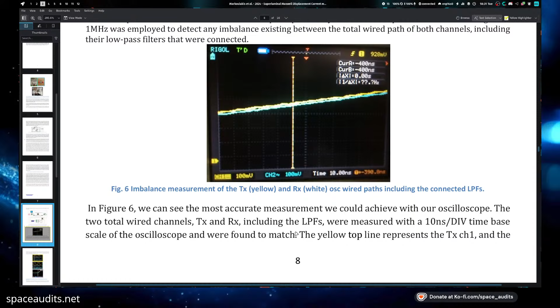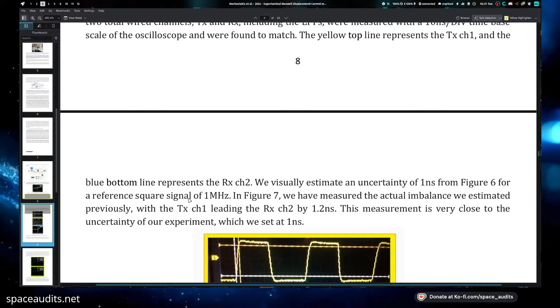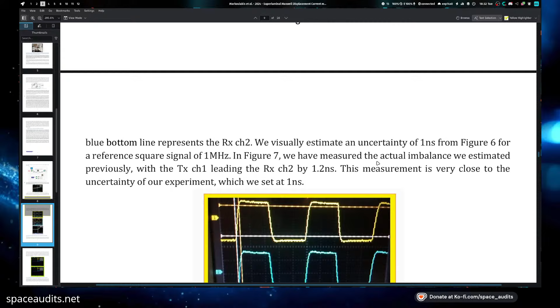Okay, so the div is time based on the scale of the oscilloscope, and the wires were found to match. The yellow line represents the transmitter at channel 1, and the blue bottom line represents the receiver at channel 2. We visually estimate an uncertainty of 1 nanosecond from Figure 6, where I reference the square signal of 1 megahertz. In Figure 7, we have measured the actual imbalance we estimated previously, with the transmitter channel leading the receiver channel 2 by 1.2 nanoseconds. This measurement is very close to the uncertainty of our experiment, which we set at 1 nanosecond.